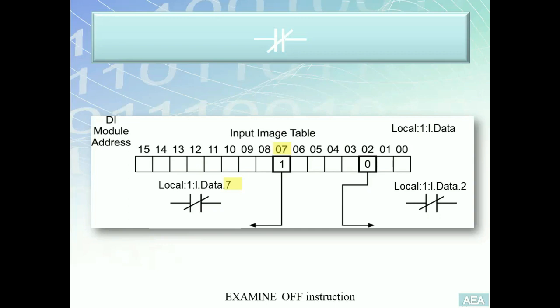Back to the XIO to the left. Right now, what type of input is wired to terminal number seven? I have no idea, but I know something for sure: this input, whatever it is, is currently in the closed state. How do I know this? Because it's currently reading one in the PLC memory.